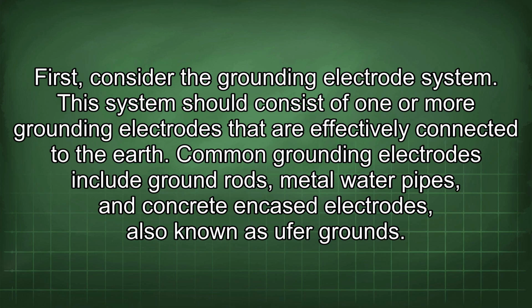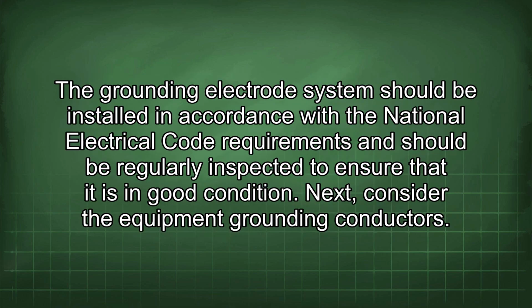First, consider the grounding electrode system. This system should consist of one or more grounding electrodes that are effectively connected to the earth. Common grounding electrodes include ground rods, metal water pipes, and concrete encased electrodes, also known as Ufer grounds. The grounding electrode system should be installed in accordance with the National Electrical Code requirements and should be regularly inspected to ensure that it is in good condition.